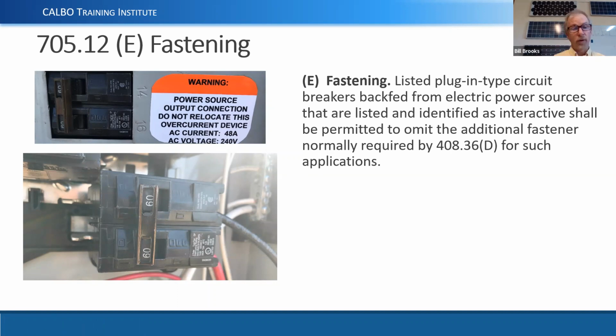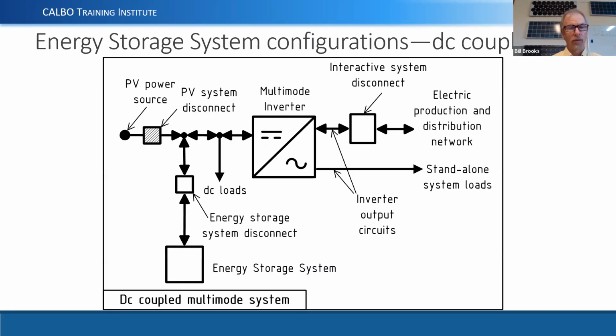However, if we're on a backup panel and we're feeding backup loads from an inverter, that is not the interactive side of the inverter. And of course, if we wanted to backfeed a circuit breaker on the backup load side of, say, a multi-mode inverter system, then that would absolutely have to be installed and fastened accordingly, the way any other backfed breaker in a sub-panel would have to be installed, according to Article 408.